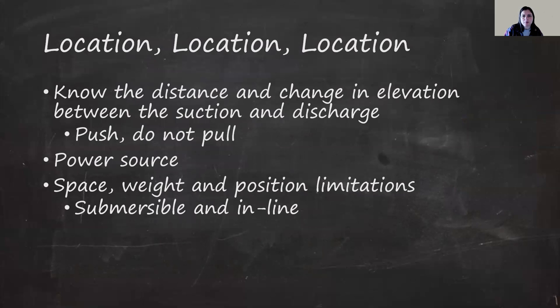A key factor in deciding which type of pump you'll need is the location where you're going to be using it. This includes where you want to place it, where you are drawing from, the influent or suction side, and where you are discharging to, the effluent or discharge side. Generally speaking, pumps have an easier time of pushing fluid rather than pulling it, so placing the pump near the influent source is usually better. You will want to ensure the pump has a proper power source. Even the smallest pumps will have the volts and amps listed on the device or packaging, but typically also include the power, such as horsepower or watts. Check and make sure that the circuit you will be operating on has sufficient current to support your pump without daisy chaining extension cords. Give the pump a stable space it needs to operate. This includes providing sufficient airflow for pumps that are air-cooled. Some pumps must be positioned in a particular fashion, such as flat, while others can be stood upright, so it's important to know what these limitations are.